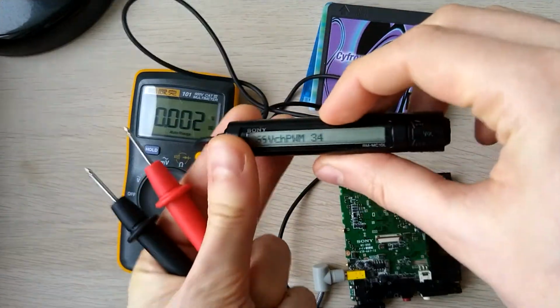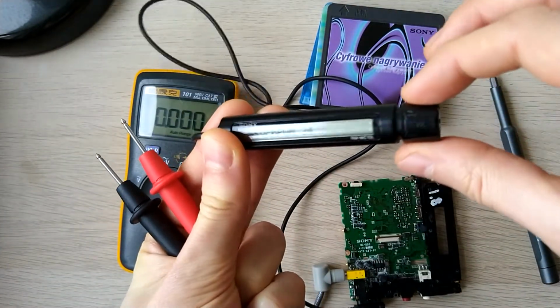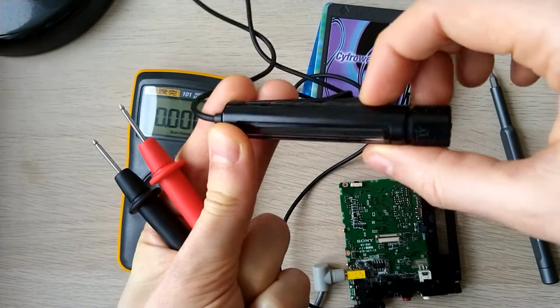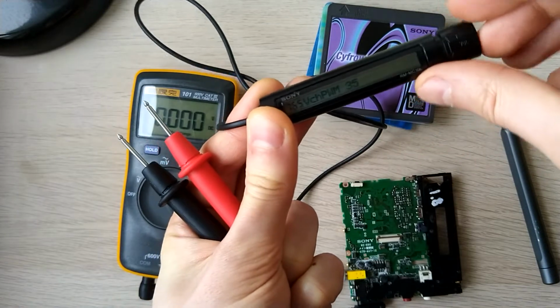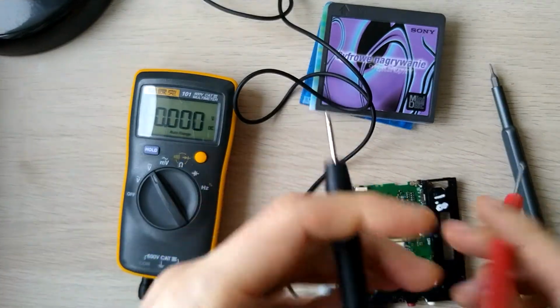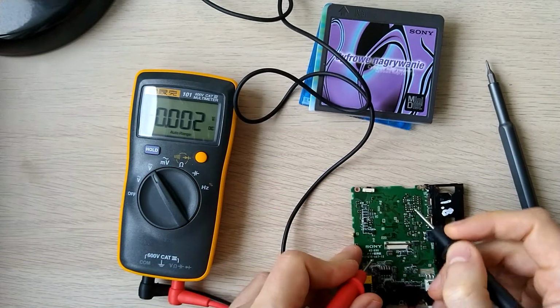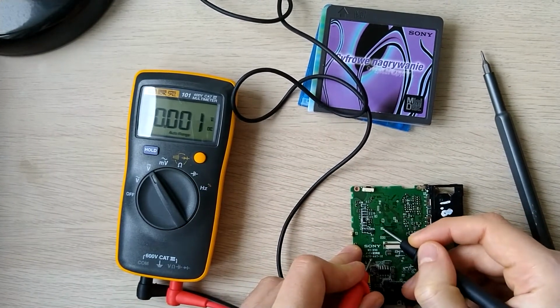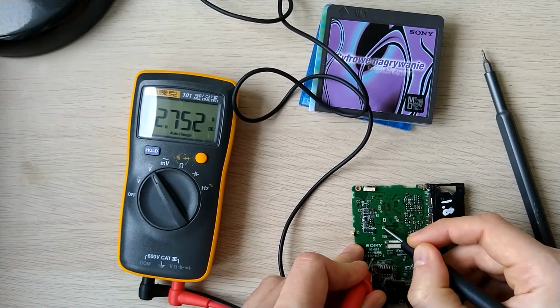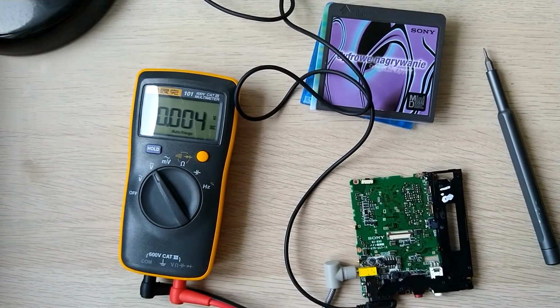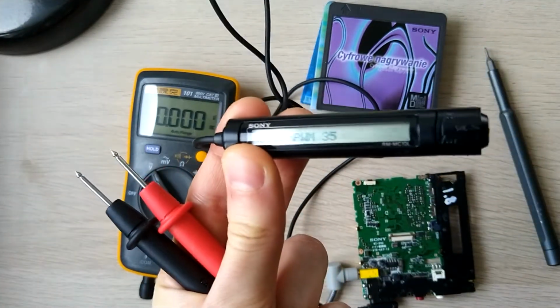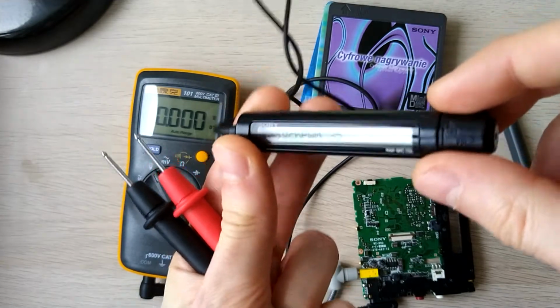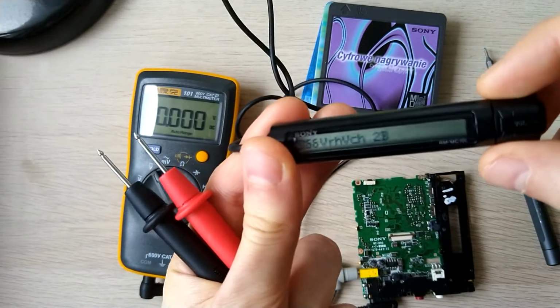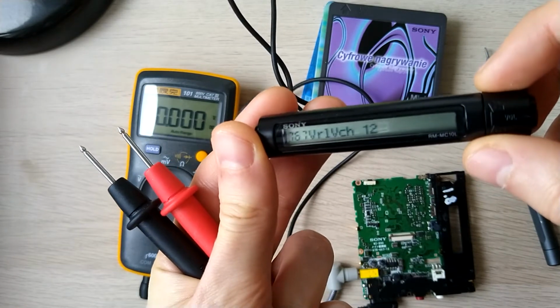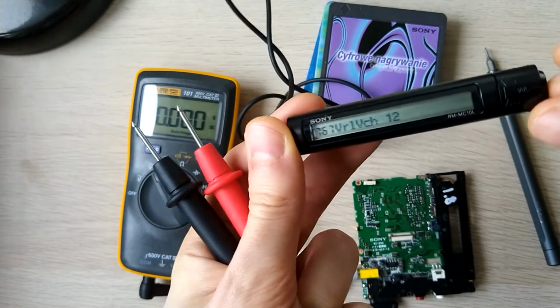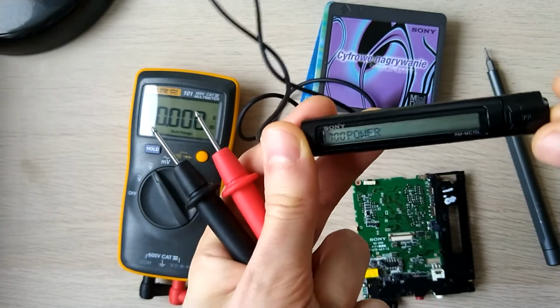If we wanted to adjust it, we can just use the volume rocker to move it up by one value, confirm by pressing pause, and now it should have gone up a little bit. Let's have a look. And it's now 2.752, which is actually closer to the reference, so we're going to leave it like that. So there are six such settings in total on this device. On other devices it may be a different number. So 762 through 767, and once all those adjustments are finished, the power adjustment is complete.